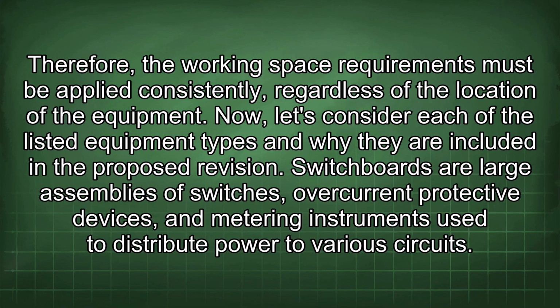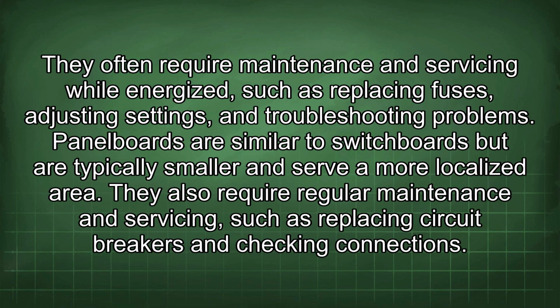Now, let's consider each of the listed equipment types and why they are included in the proposed revision. Switchboards are large assemblies of switches, overcurrent protective devices, and metering instruments used to distribute power to various circuits. They often require maintenance and servicing while energized, such as replacing fuses, adjusting settings, and troubleshooting problems. Panel boards are similar to switchboards but are typically smaller and serve a more localized area.